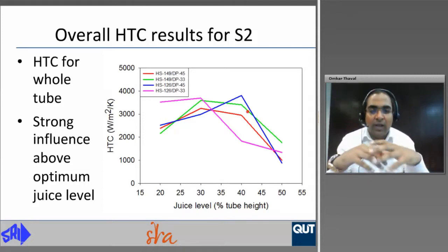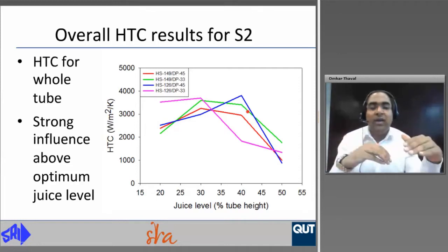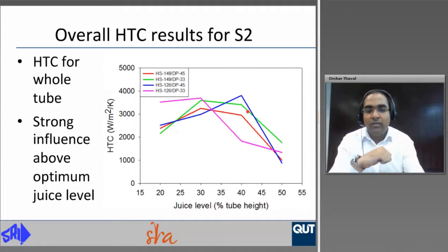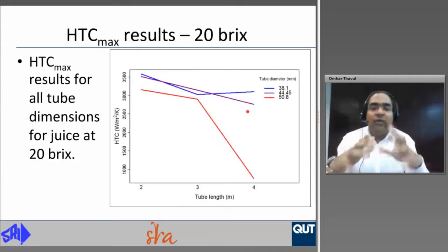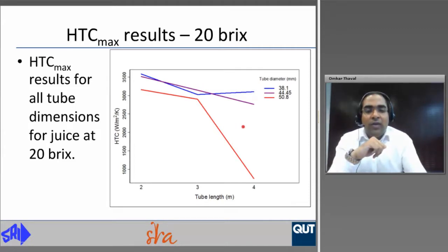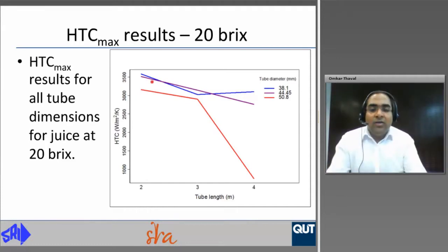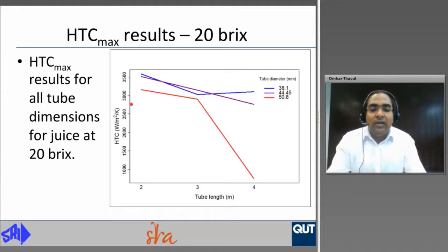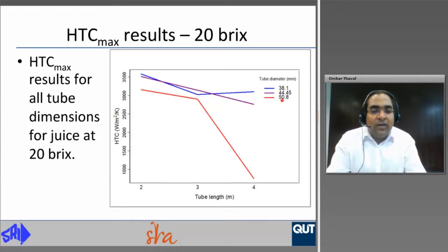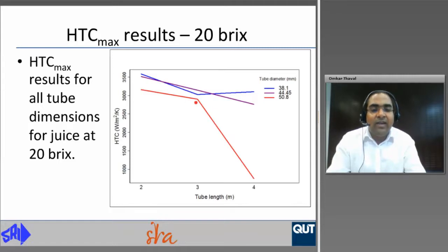All results were assembled and the optimum juice level where maximum heat transfer coefficient was achieved was reported. For 20 brix, all 9 tube dimensions with HTC max results show that 38.1 and 44.45 mm tube diameter at 2 and 3 meter lengths give heat transfer coefficients above the benchmark of 3,000 W/m²K. The 50.8 mm diameter has high heat transfer coefficient at 2 meter length with a slight decrease at 3 meters, but there is a steep decline in heat transfer coefficient when 50.8 mm diameter and 4 meter tube length is used.